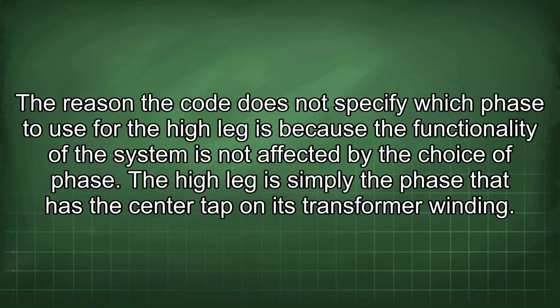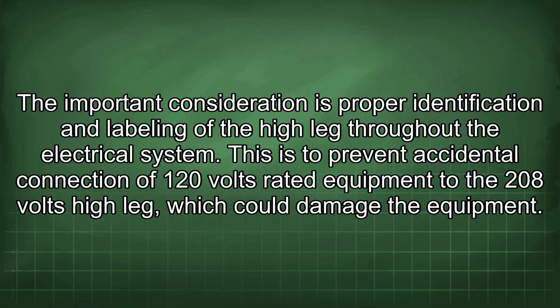The reason the code does not specify which phase to use for the high leg is because the functionality of the system is not affected by the choice of phase. The high leg is simply the phase that has the center tap on its transformer winding. The important consideration is proper identification and labeling of the high leg throughout the electrical system.